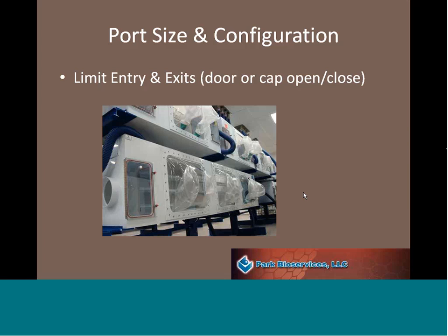So perhaps as important, maybe even more important than the chamber size is the port size, because that's how you're going to bring materials in. And again, it may seem like I'm being redundant here, but you really want to limit the entries and exits. And so here, if we see in this picture, it's kind of an ideal picture. You have a door where you enter the supplies, but if you look to the left of the door, you're going to see a 12-inch port. That would be an additional way of getting supplies in.